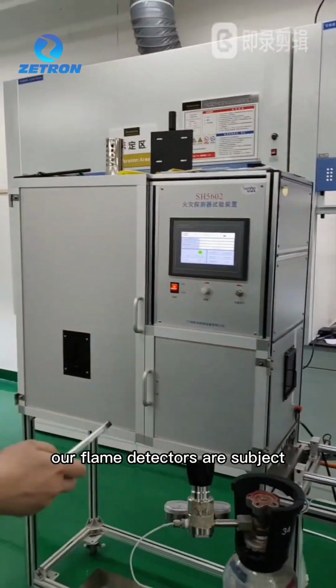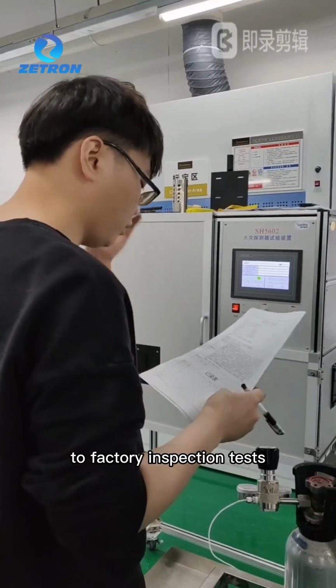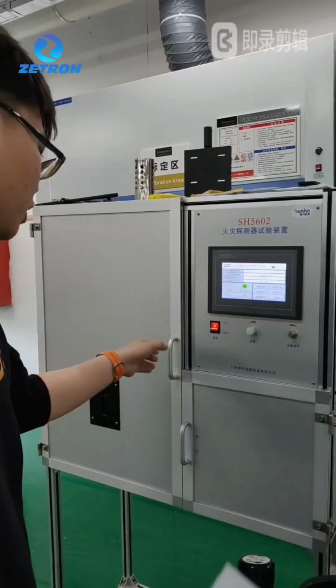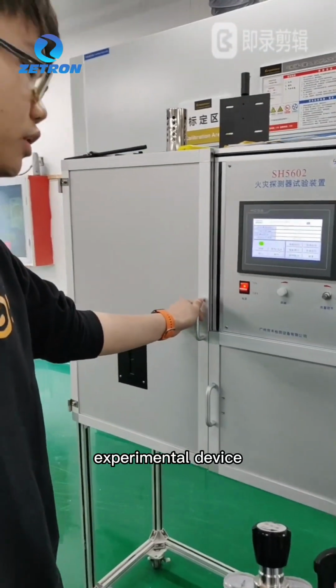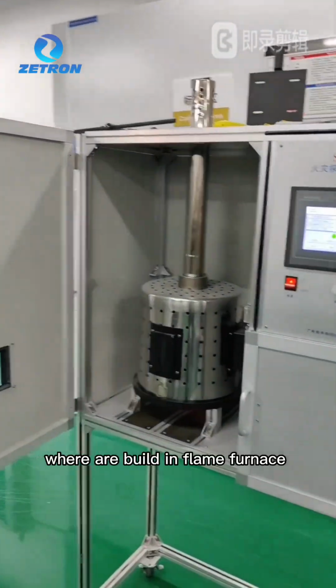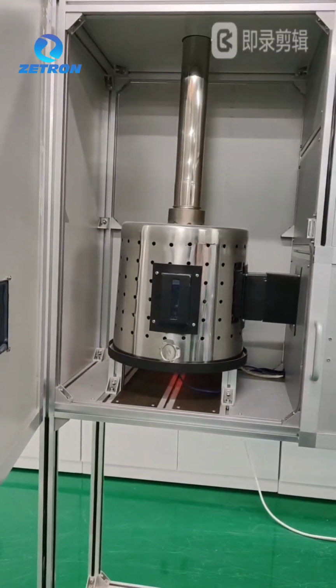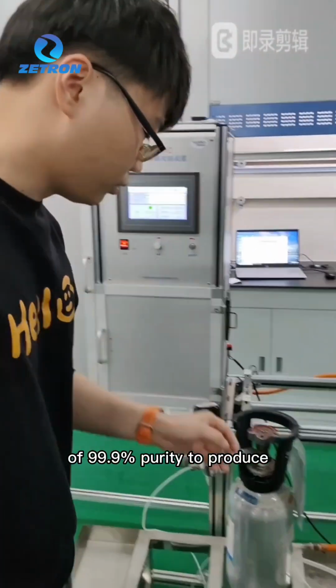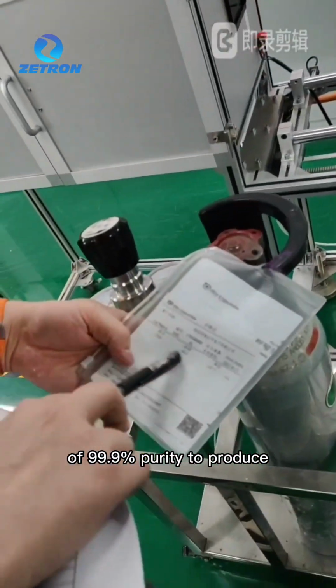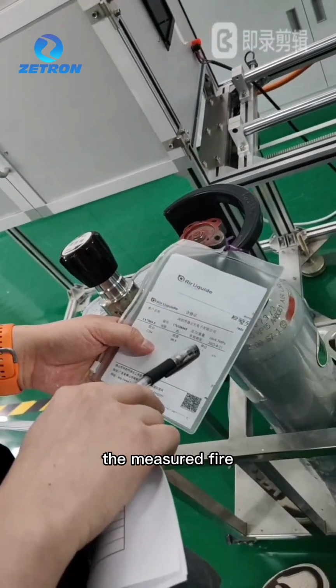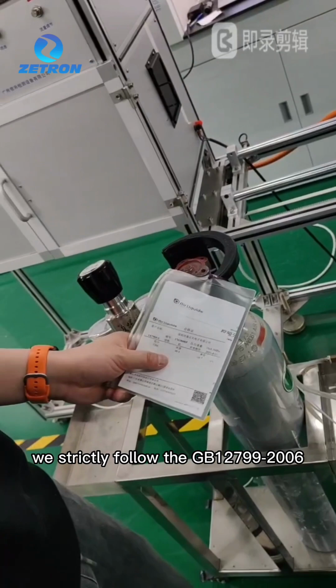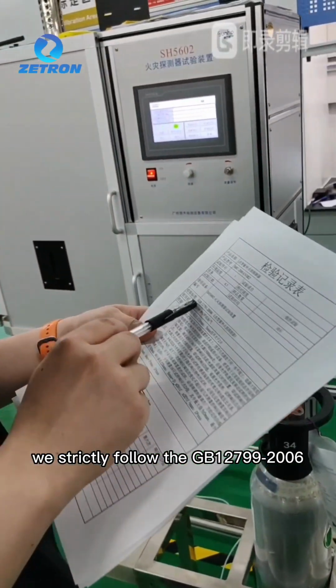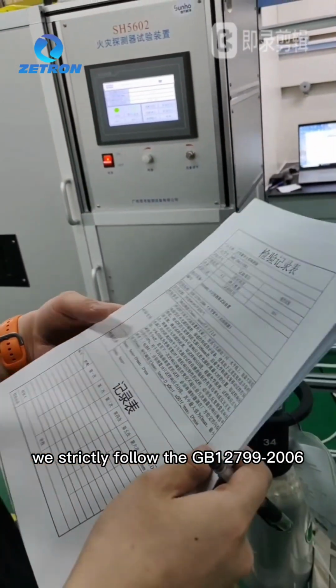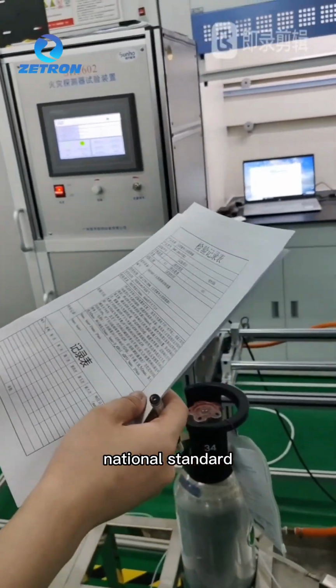Our flame detectors are subject to factory inspection tests. This is a flame detector experimental device, with a built-in flame furnace. By burning methane gas of 99% purity to produce the measured fire, we strictly follow the GB 12799-2006 national standard to conduct experiments.